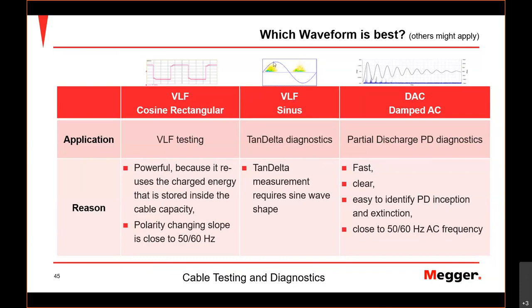But keep in mind you only have 2.5 seconds to charge all your cable capacity. And then you burn away your voltage for 2.5 seconds and it's lost. It cannot be recuperated. And then you recharge with negative polarity. Also, you only have 2.5 seconds, and then you burn away the energy. So you only have 2.5 seconds to charge your whole cable capacity. And that is the limit of that testing method, because you can test only a shorter cable length with that.